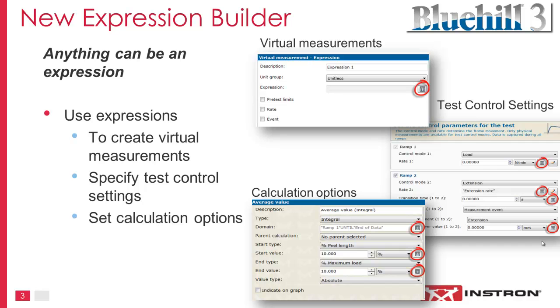Another place where this expression ability helps is test control settings. For example, if you have different ramps in your test — ramping up, then holding, then ramping down — many of the parameters you define can now be not only numbers but expressions. You can really embed a lot of logic into the way you are handling your ramps.